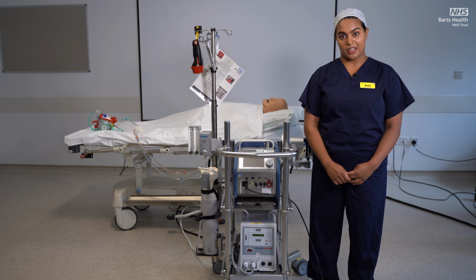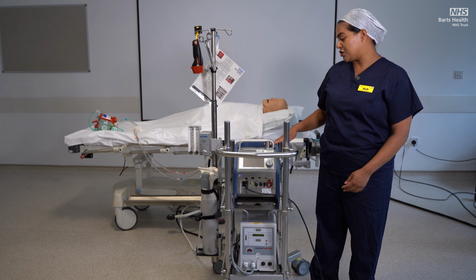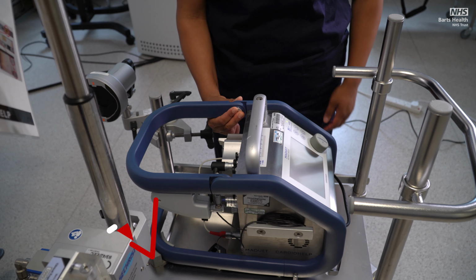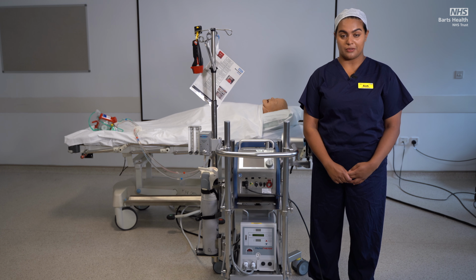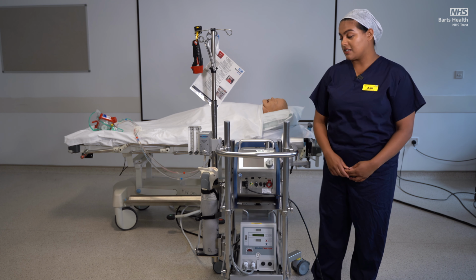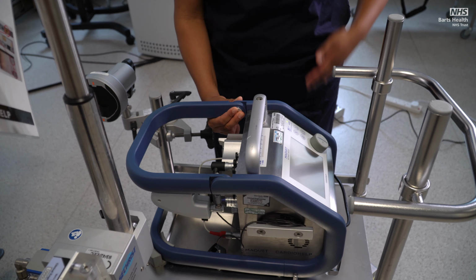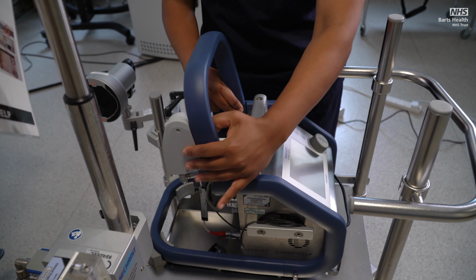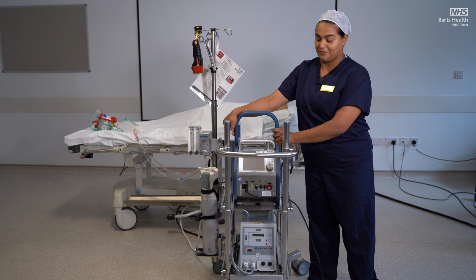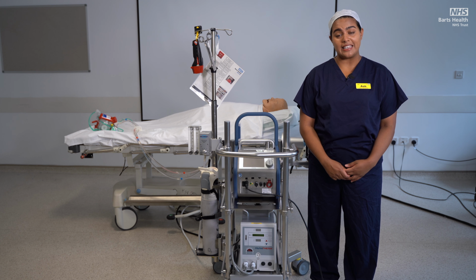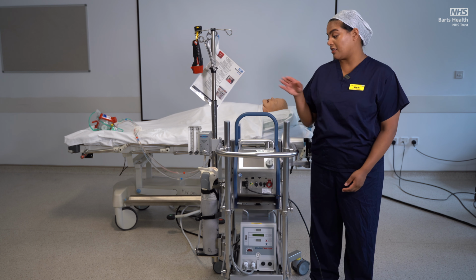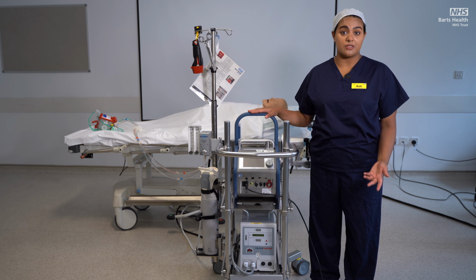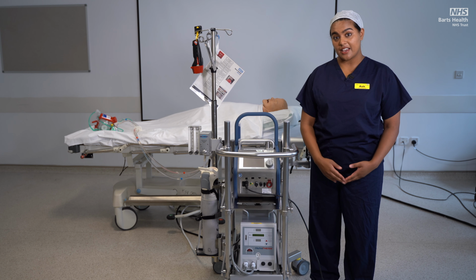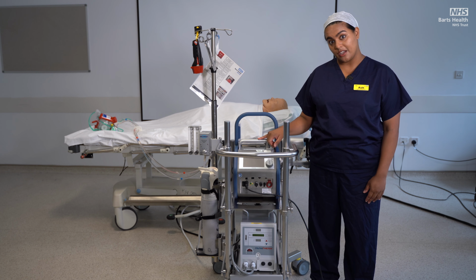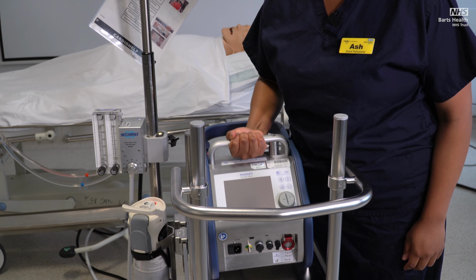When the patient is on ECMO, the blue guard should be kept in the horizontal position to protect the oxygenator disposable. If the user requires access to the oxygenator, simply press the two buttons found on the Cardiohelp, lift up into the vertical position. The Cardiohelp should never be lifted or carried using the blue guard, because this will cause damage to the guard. Instead, use the metal carrying handle to do any manual handling on the Cardiohelp.